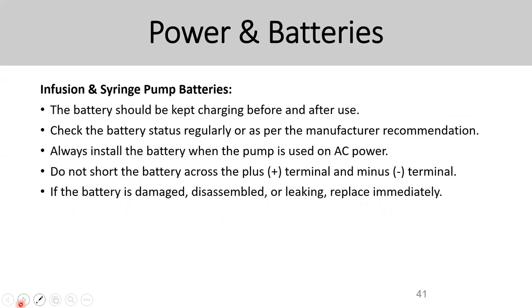Always monitor the system, check the volume remaining in the syringe, and replace at 70–80% full — do not depend solely on the alarm feature. Patients may require continuous infusion or multiple drips. Clinical operators must label each pump and tube when using more than one syringe pump to identify which drugs are in which. Regarding power and battery: always keep the battery charged before and after use, check battery status regularly, do not short the battery, and replace immediately if it is damaged or leaking.